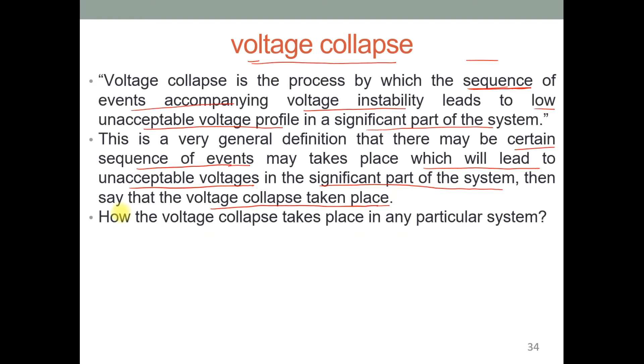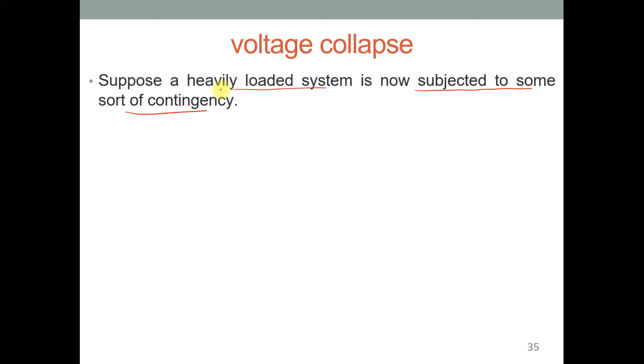So let us understand how voltage collapse takes place in a particular system. Suppose a system is initially operating with heavy loading condition. In the sense, the transmission lines are heavily loaded, that means the lines are transferring power up to the maximum power transfer limit. Clear? So we have limited reactive power sources in the system. Suppose the generators are fully loaded or quite far from the load, that means long distance power transmission lines. In such a case, if the heavily loaded system is now subjected to some sort of contingency, that means a line outage or generator outage or any fault occurs, then a transmission line or generator outage will take place.